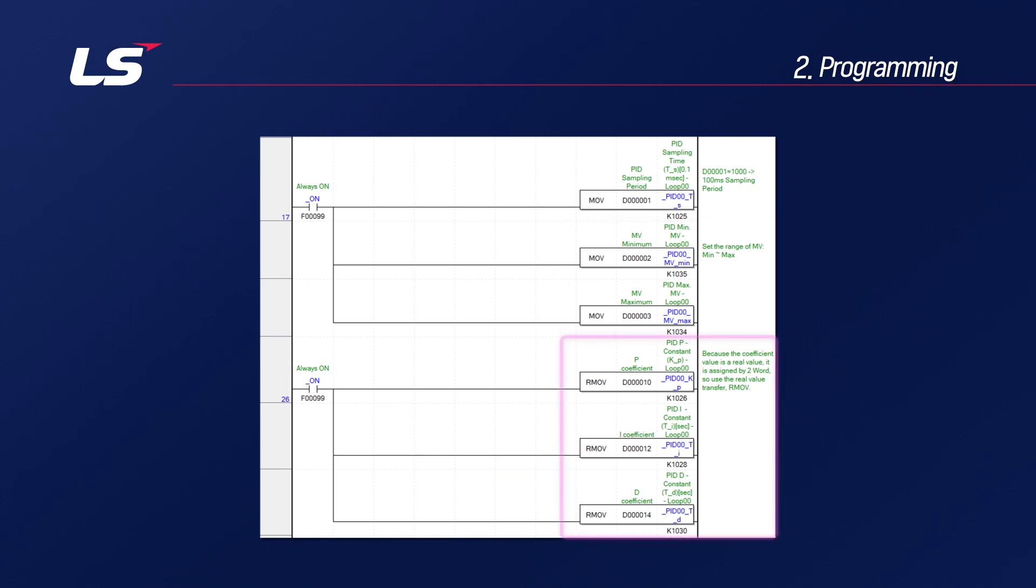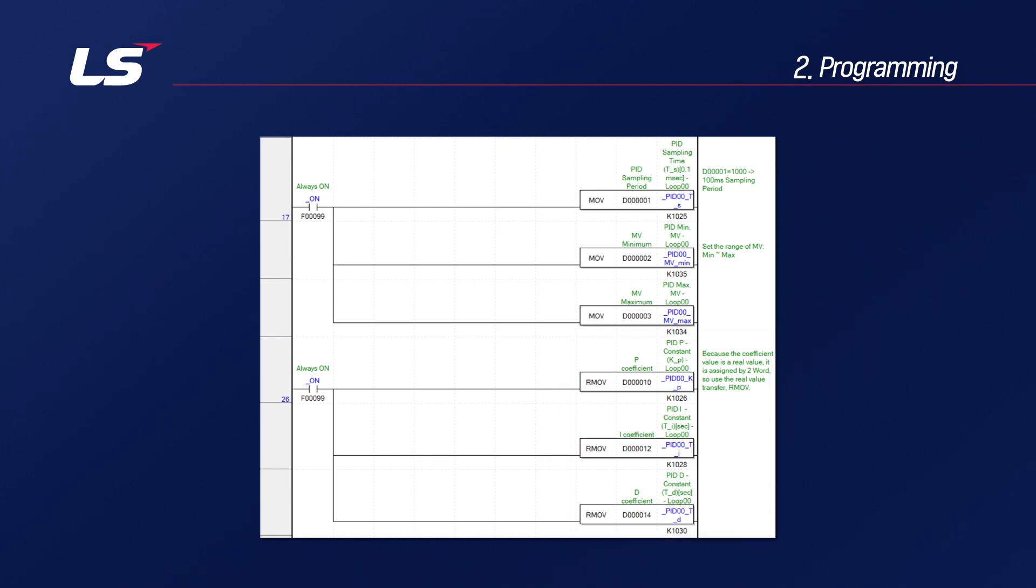You can add P, I, and D coefficients, but if you want PI control, you don't have to add D value. These coefficient values are allocated two words in real type, so please be careful not to overlap the addresses. So far, the contents of this program are the basic parameters used for PID control.